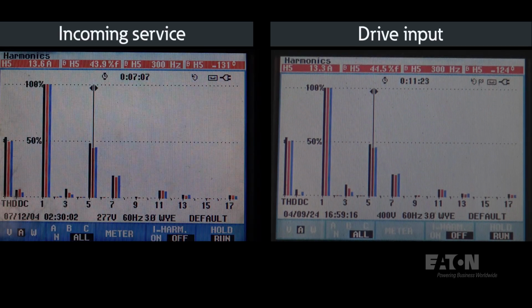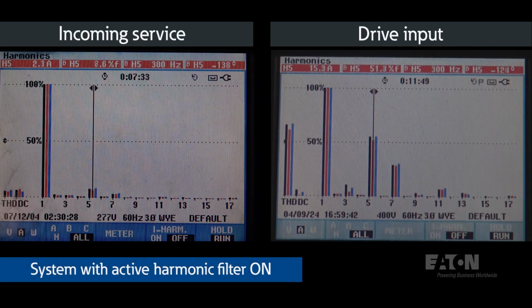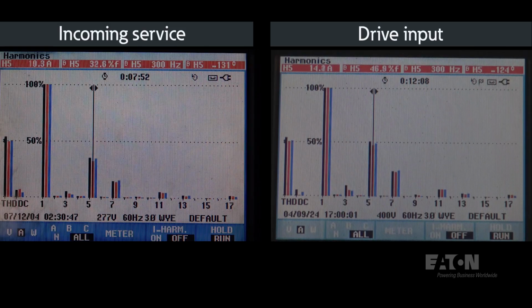So right now we're looking at phase B, and the fifth harmonic current is 13.6 amps. And if I look at my input to the drive, it's basically the same. So now I'm going to turn on the active harmonic filter, and what you'll notice is on the incoming service, of course, the harmonics go down because we're injecting equal and opposite harmonics. But now you can see that the harmonics at the drive have actually increased a little bit, over 15 amps now. So we've actually increased the harmonics coming out of the drive by adding in the active harmonic filter.